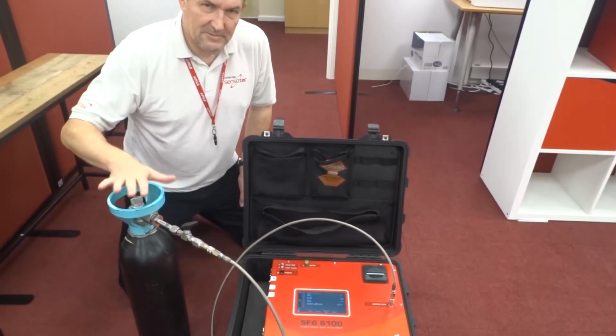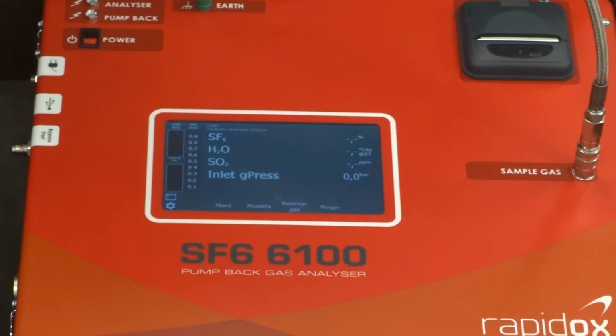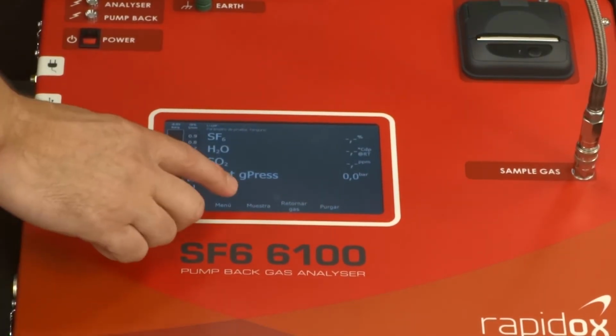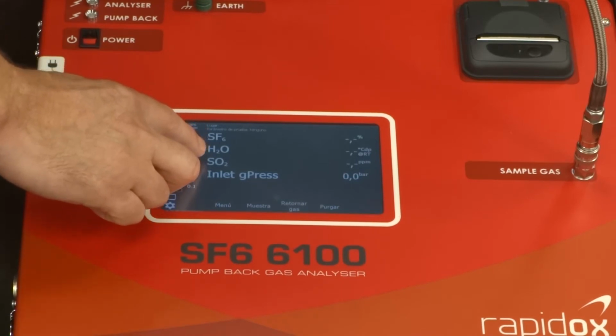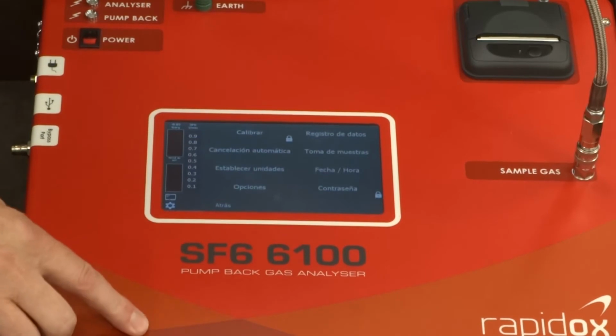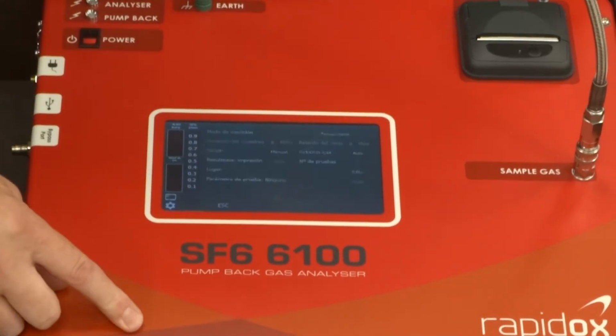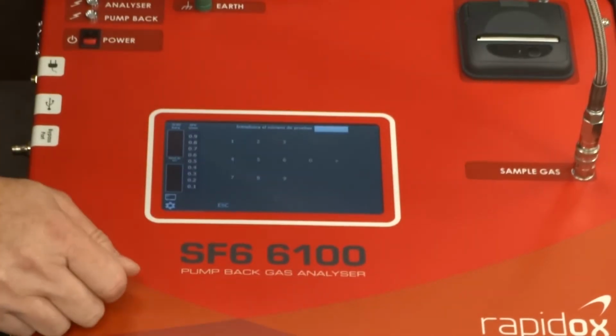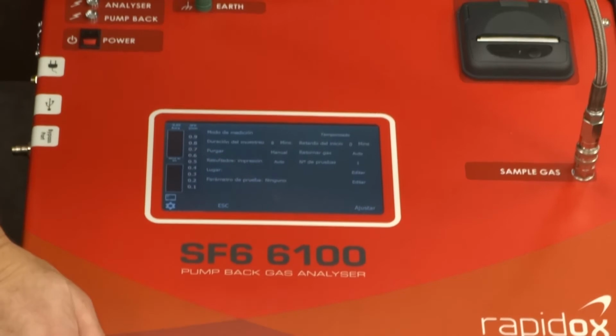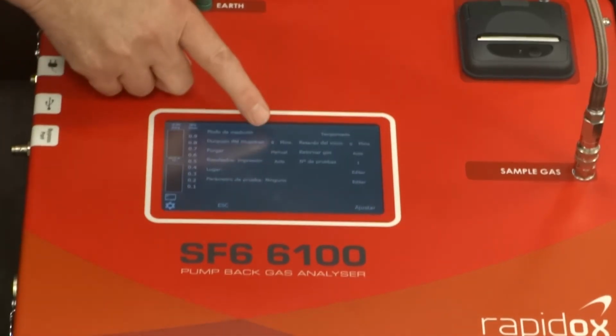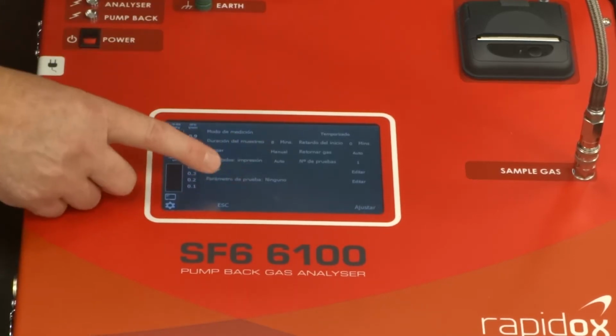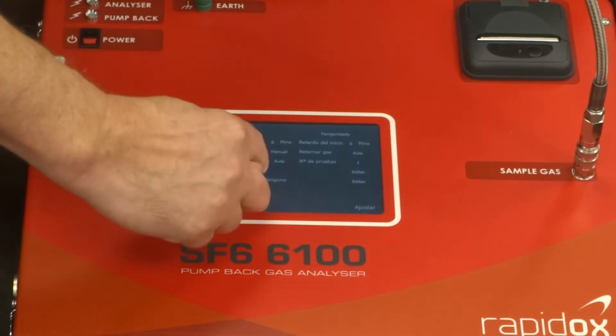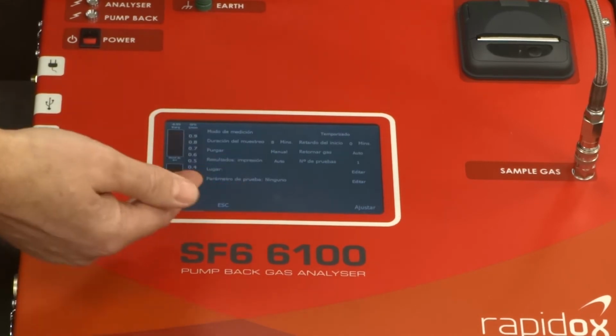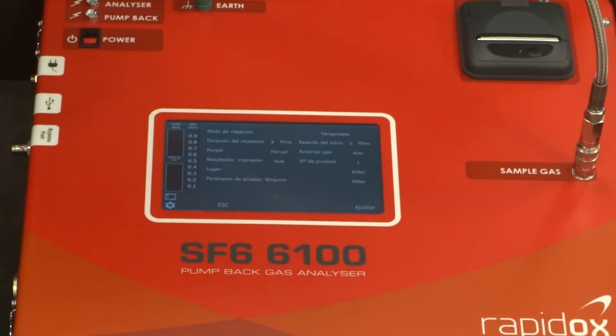There's approximately 7 or 8 bar of gas pressure of SF6 inside here. So I'm now going to demonstrate a single test. We're going to measure SF6, water, sulfur dioxide and the pressure. I first want to check that the parameters are correct by pressing the sampling option. I'm going to do one single test, so I'm just going to select one test. This test is going to run for 8 minutes, which is standard to measure water and SF6, and we're going to automatically pump back, and when it's finished, the test will also do a printout of the results.